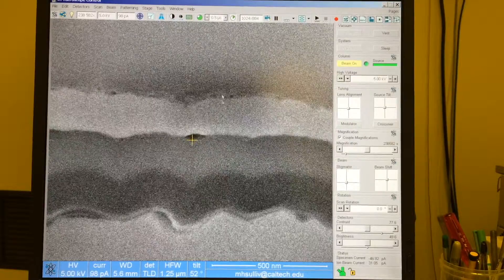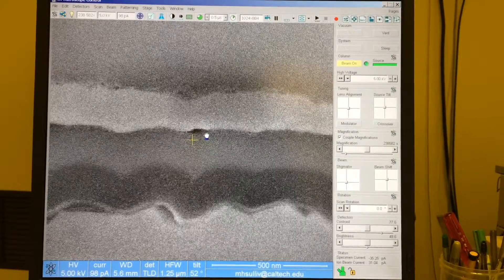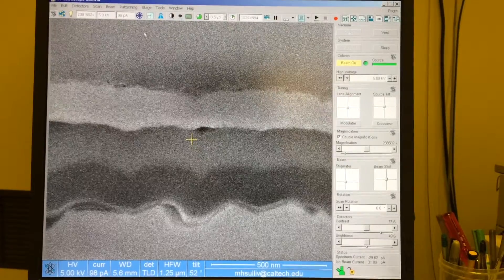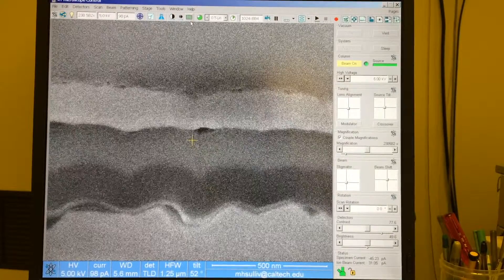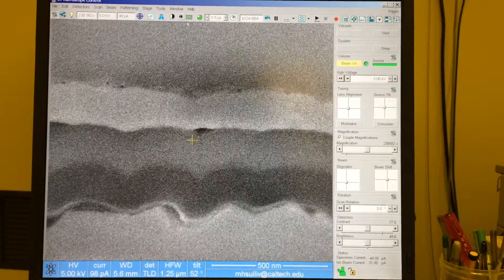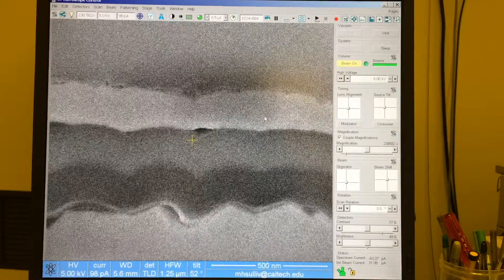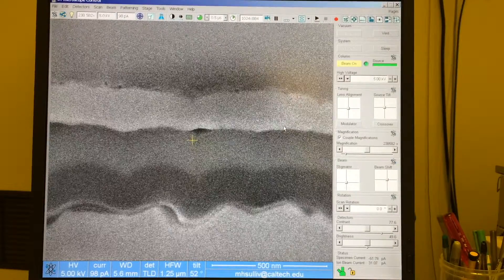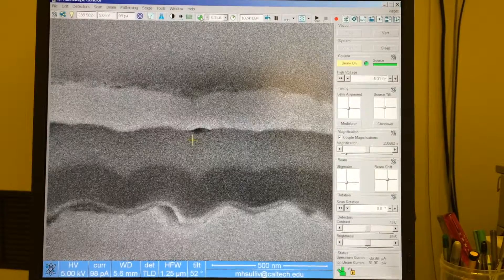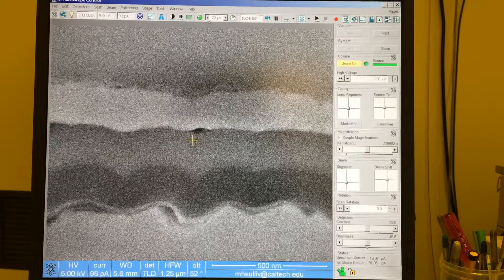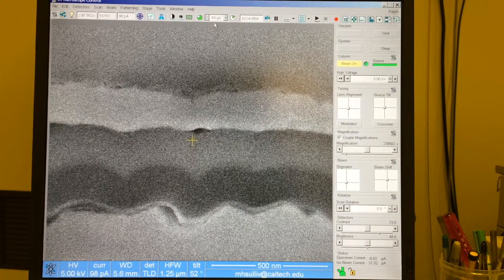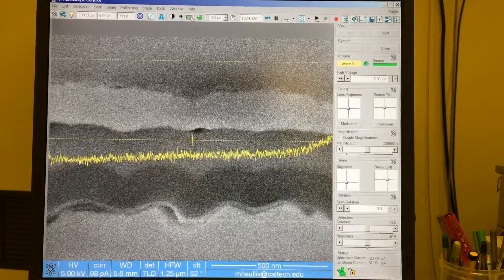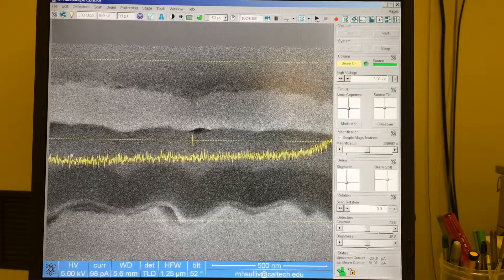Now lastly, what we can do is use our beam shift to position us the way we want. But we always want to perfect or at least adjust the brightness and contrast. It might be a little bit different for what's useful for an alignment versus what's useful for the final picture. So I'm going to pick my dwell time that I want for this image, and I'm going to choose 60 microseconds in this case. And then to check the brightness and contrast, I'm going to turn on the video scope.